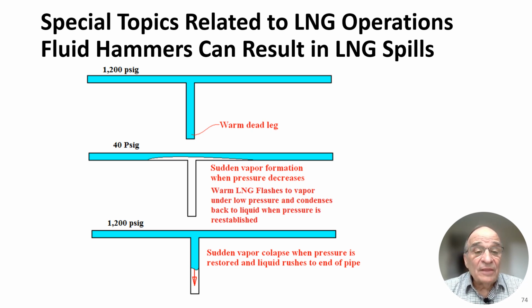Now all of a sudden, you have an emergency shutdown or some type of shutdown, and the pipe depressurizes. Here I just selected 40 psi gauge, and now this warm LNG vaporizes and leaves a long leg of vapor. Now you restart the plant, and it goes back up to 1200 psi. The vapor collapses and goes back into LNG, and as it does so, a very rapid, fast stream of LNG is heading to this dead end.